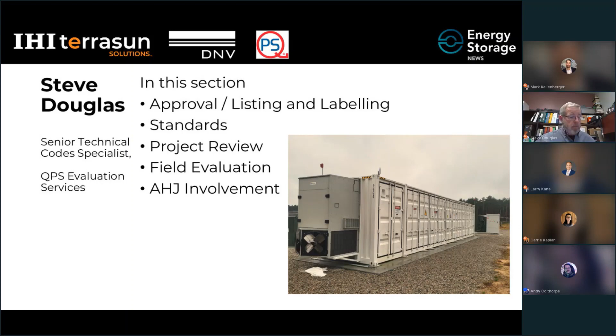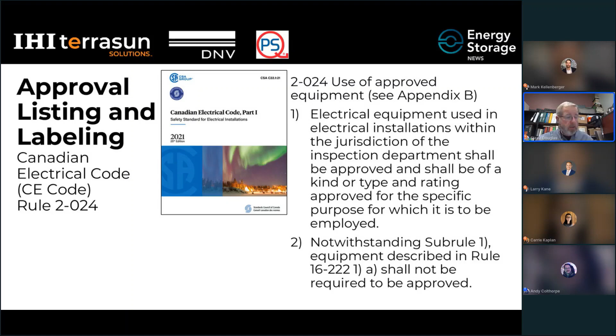We'll start first by looking at the Canadian Electrical Code, which requires that all electrical equipment, including energy storage systems, be approved. Approved in the Canadian Electrical Code gives two options: full certification or field evaluation. Full certification is where the certification organization reviews the product and gives the manufacturer permission to place the certification mark on it. Field evaluation is where a field evaluation body or inspection body looks at each individual unit and puts a field evaluation label on each one.